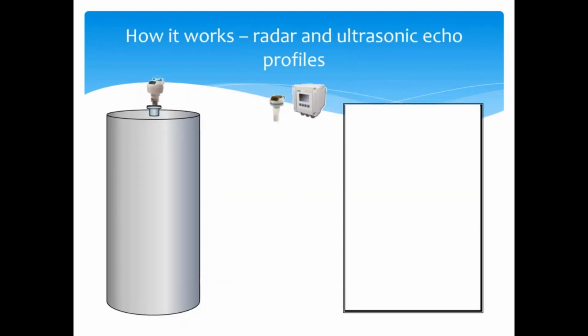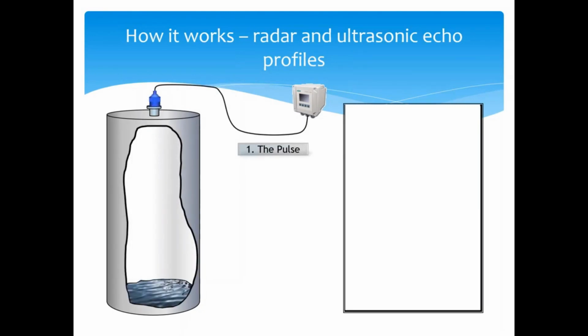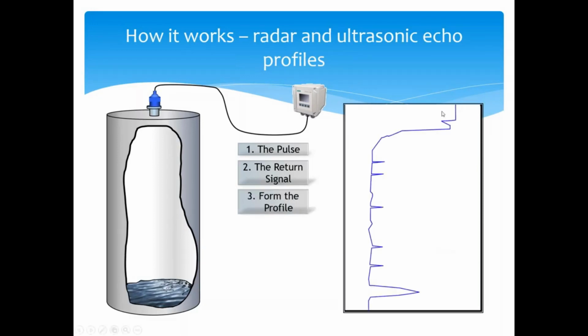So talking about how this works and how that echo profile is generated. Whether I've got an ultrasonic or a radar up on top of my tank makes no difference to me. What we're doing here is we're sending out that pulse. Whether that pulse happens to be an ultrasonic sound wave or a radar wave makes no difference. We then get a signal return and we form that echo profile. Once we form that echo profile, we then do some filtering. So if I look back here, I have these little short, quick spikes. Those are not caused by signal return. They might be from ambient, some sort of noise in the background.